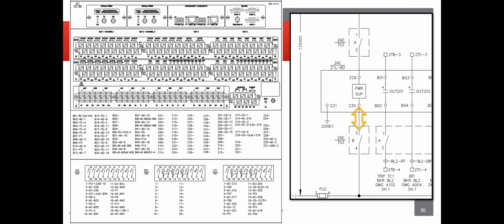So we've got the comparison now between the wiring diagram and the DC schematic. This is always a good check as well, to verify that the wiring matches what you have on the functional circuits. So whatever the electricians installed matches what you are going to be testing, pretty much.